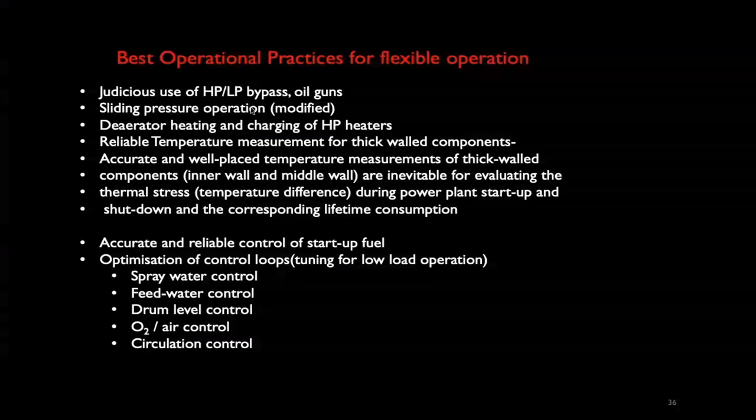Deaerator heating and charging. I'm not happy to mention here that I put it in a best practice. This is a regular practice, but as people are not doing it widely, I could put it here. This is a best practice which was being followed a long time back, but we have gone back. I start doing this. Reliable temperature measurements. Without control you won't be able to put anything in your control and then change your process.